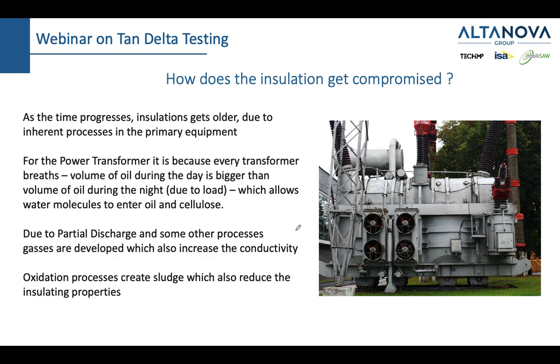So partial discharge inside the transformer is a process where we have small sparks, let's say between the high voltage and the low voltage, or maybe two windings, etc. And in this process, the gases are developed. And unfortunately, the gases also increase the conductivity of our insulating system, which is a problem. Also, we have an oxidation process, which creates a sludge, which also reduces the insulating properties and increases the conductivity. Acidity changes, and all this contributes to the deterioration of insulation.